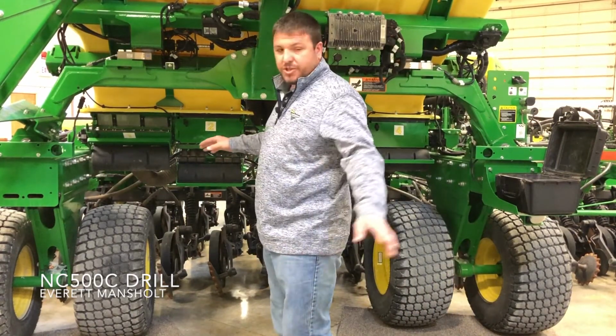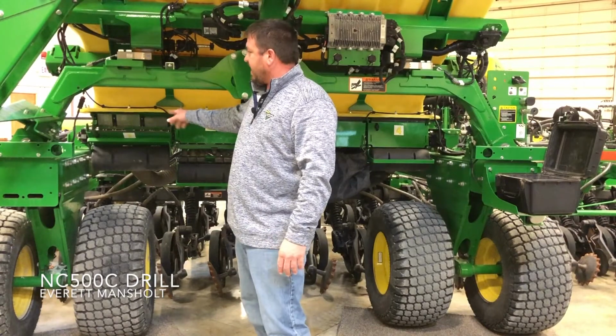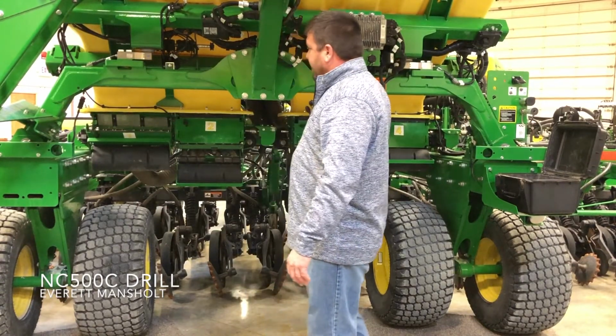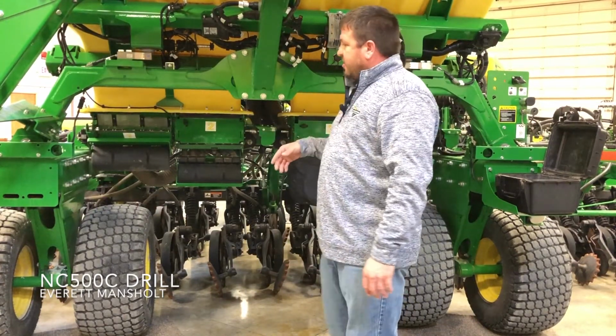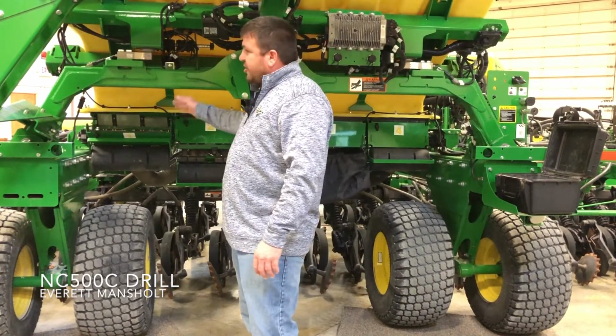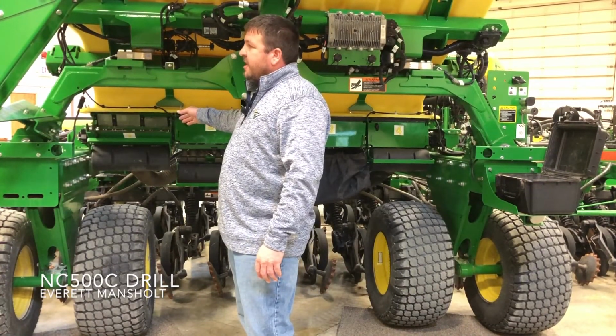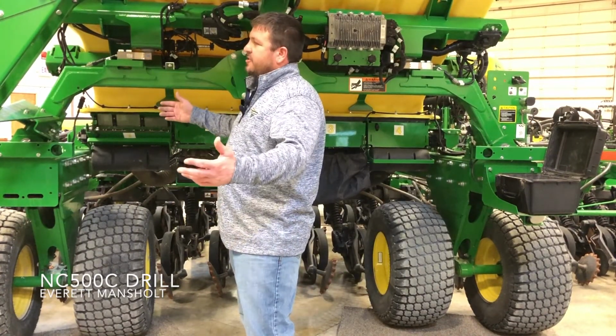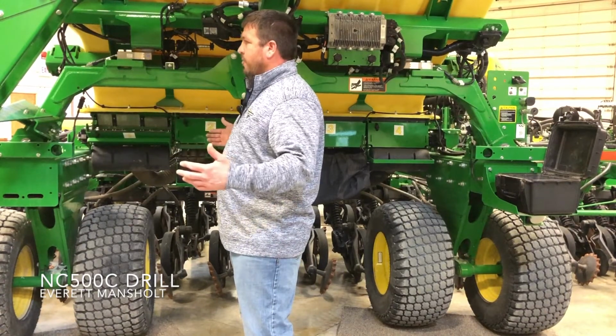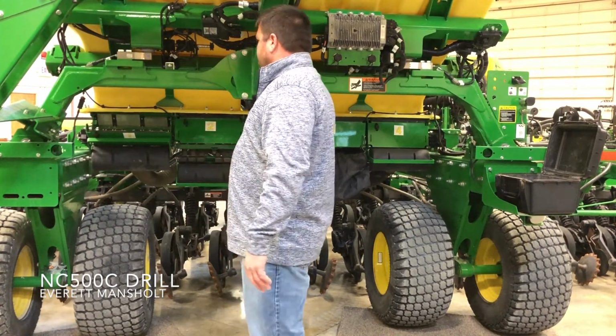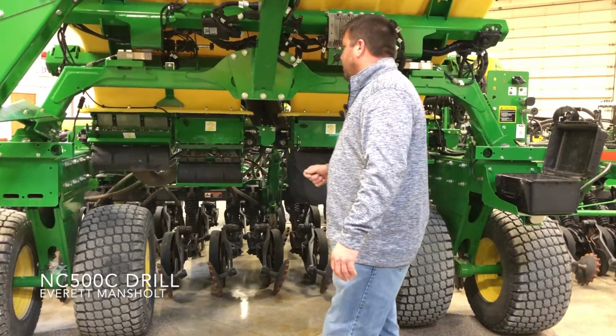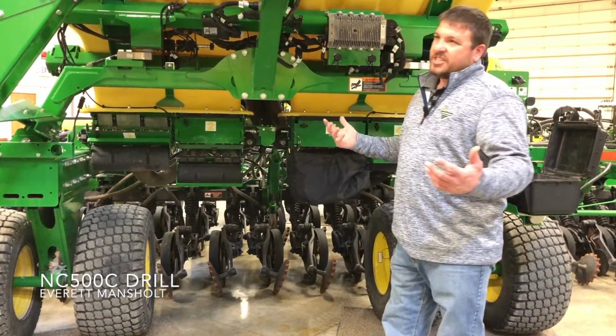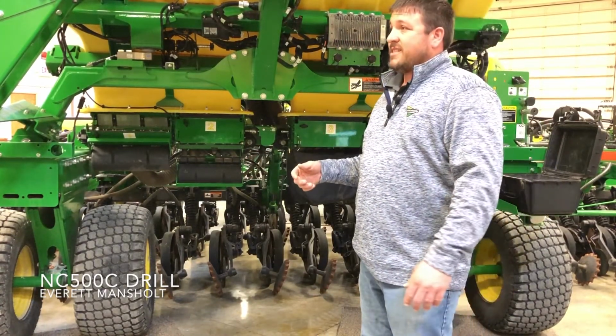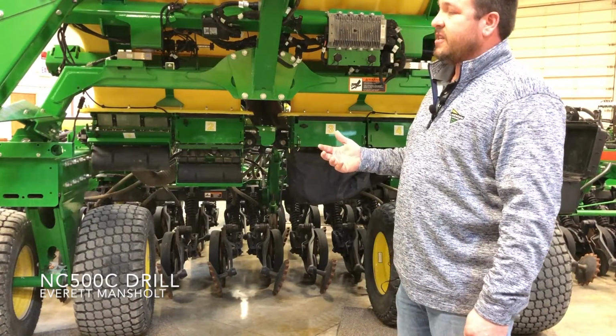You can go in, we'll show you on the monitor - you can calibrate each meter individually. It also gives you the option to calibrate the first meter, and then it'll ask if you want to use that calibration for all four meters. You can go ahead and do that. When I've run it, I've just calibrated all four because it's that fast to do.